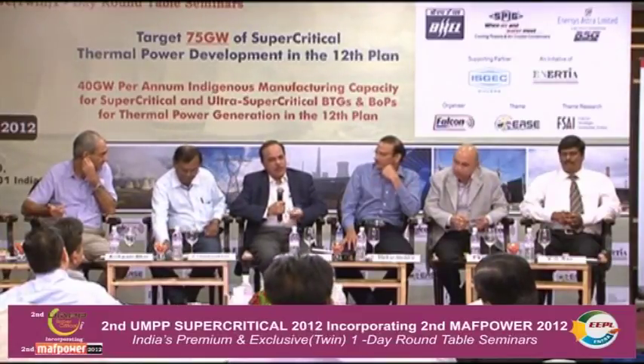In the late 1960s, the US came out with supercritical technology. In the late 90s, they went for renovation and modernization of those plants, but not all were renovated, and many orders were cancelled. When I was in Toshiba, we got the maximum orders from the US for renovating supercritical plants, but within 5 years they were all cancelled because they realized they were spending much more money while the output gain was not so much. You need to understand that technology development in mechanical engineering happens every 15 years. If you still want to upgrade 30 or 40-year-old technology to the latest technology, you have to spend a lot of money. And if you don't change to the latest technology, you're compromising - you're just increasing the life, but not really getting the output. You still can't get the same heat rate or economics, so that's why they were cancelled.